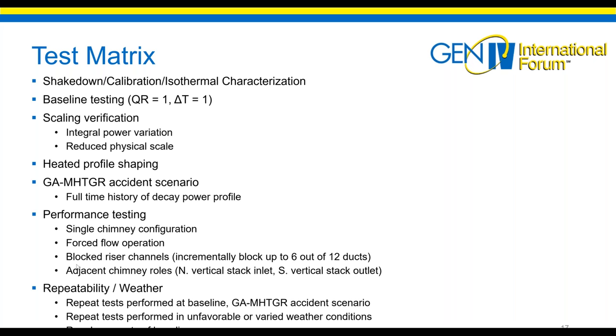The other thing that wasn't noted here, which I thought was very notable, is that we did a test where we looked at ingress, instantaneous ingress of a large volume of heavy gas, which in this case we used argon. That was done to look at a situation in case you had the plant co-located with some kind of chemical industry plant that you were supplying power to, and if there was some situation where there was a discharge from that plant that was fed into the inlet to the cooling system, whether that would impact the operational aspects. We found that it did, but it was a short-term effect, and after a matter of minutes, the system was able to recover and it reestablished normal flow.